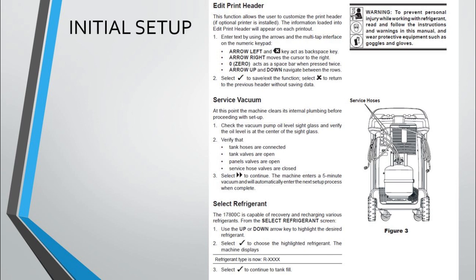Service vacuum. At this point, the machine clears its internal plumbing before proceeding with setup. 1. Check the vacuum pump oil level sight glass and verify the oil level is at the center of the sight glass. 2. Verify that tank hoses are connected, tank valves are open, panel valves are open, and service hose valves are closed. 3. Select double arrow to continue. The machine enters a 5-minute vacuum and will automatically enter the next setup process when complete. Select refrigerant. The unit is capable of recovery and recharging various refrigerants.